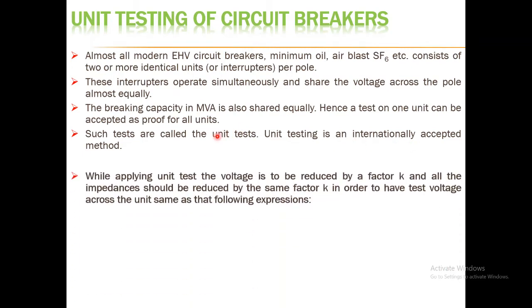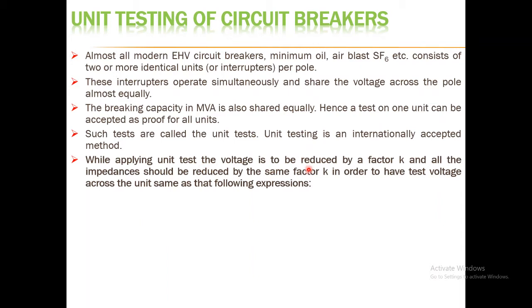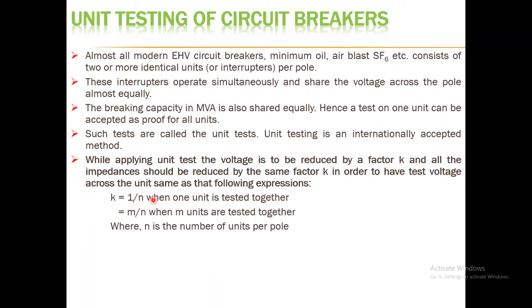While applying unit test, the voltage is to be reduced by a factor of K, and all impedances should be reduced by the same factor K, in order to have the test voltage across the unit equal to the calculated value. K equals 1/N when one unit is tested, and K equals M/N when M units are tested together, where N is the number of units per pole. So this is the factor by which one has to reduce both the voltage and the impedances.